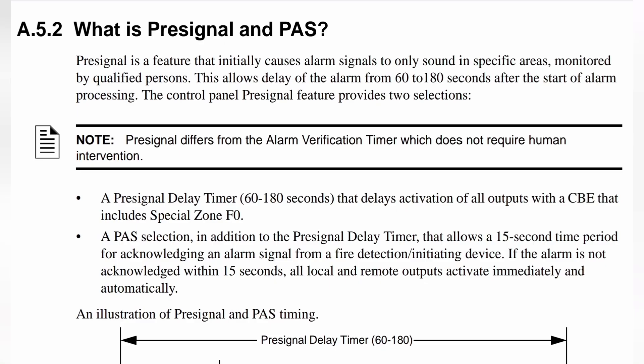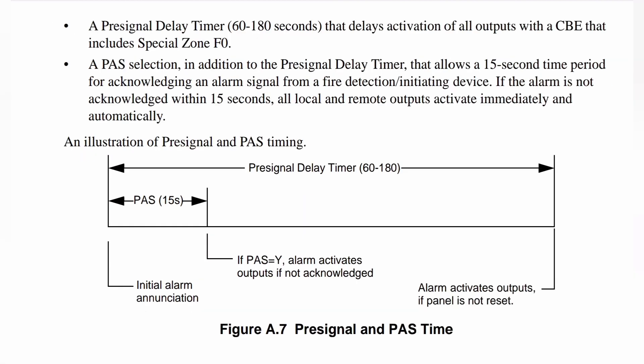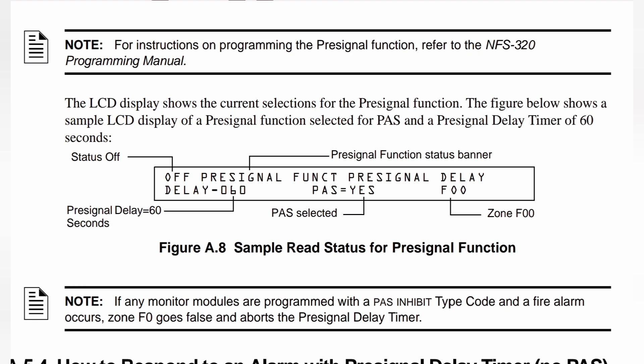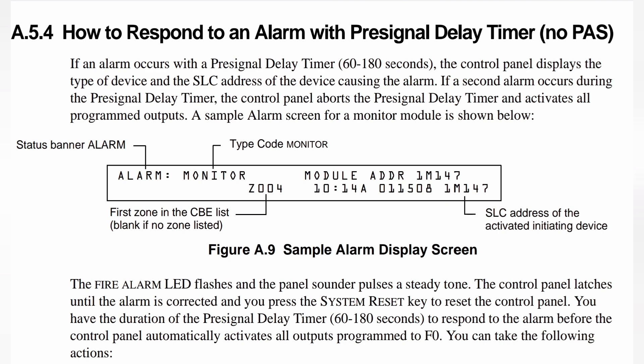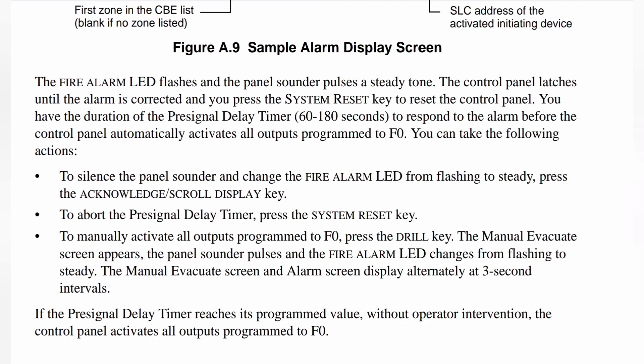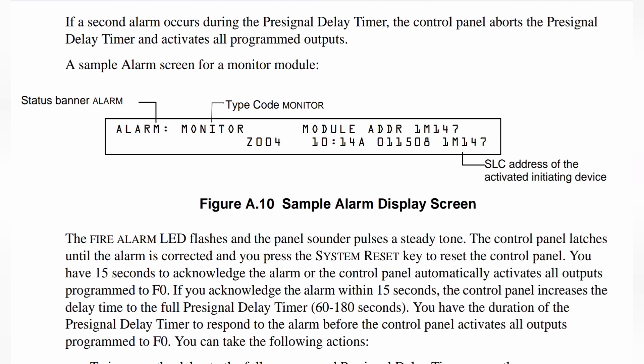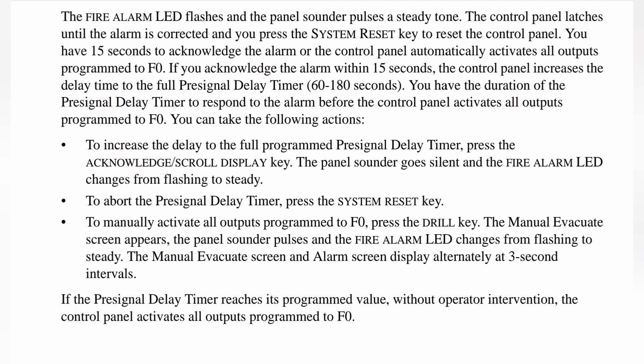The purpose is to give facility staff a short window of time to check the validity of the alarm before a full alarm activates and the building evacuation plan starts. Full activation occurs if trained personnel do not reset the alarm within a specified period of time, which can typically be programmed up to a three-minute delay, or if another device detects fire conditions.